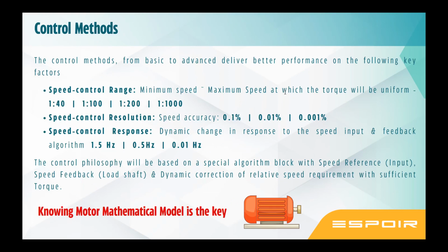Now it is not just about the pulse per revolution. It is also about how well your algorithm works. Another advantage of a control method is response. How dynamically it adapts to the speed you ask the VFD to go. Motor has to adapt to the speed. In a basic control method, it takes time. In an advanced control method, it works fast. Motor dynamics are going to be the same, but the way the drive dynamically changes is going to be different in the advanced control method. So it is how fast it changes.